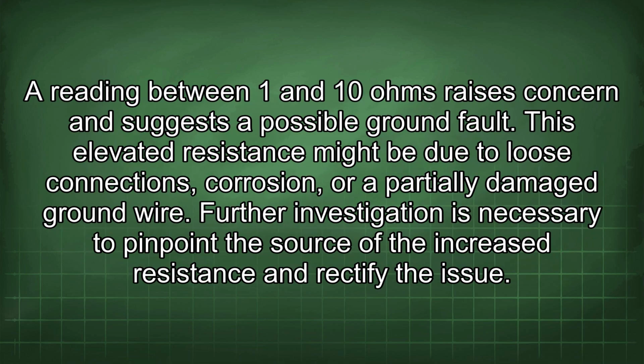A reading between 1 and 10 ohms raises concern and suggests a possible ground fault. This elevated resistance might be due to loose connections, corrosion, or a partially damaged ground wire. Further investigation is necessary to pinpoint the source of the increased resistance and rectify the issue.